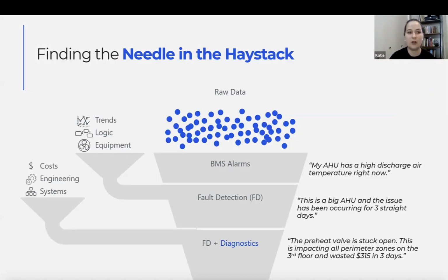So, a real broad brush definition of fault detection and diagnostics and how that corresponds to finding this needle in the haystack. Your building automation system, your building management system, I'll call it a BMS from now on, is what operates your HVAC system in your building and potentially your lighting system. Let's focus on just HVAC for this example. So you have lots of data coming in, different data points telling you temperatures, valve positions, damper positions, and all that information comes in, and your BMS then tells the building what to do and will sometimes alarm if something is far out of range to the point where it needs a quick response. An example of that would be your air handling unit is discharging a very high temperature right now and it's serving, and that's all you know about it.